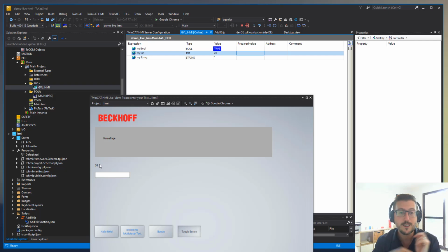So there we go. Where that was starting to go a little bit haywire then, that's a good example of if you are developing on a live machine, this is how you do it. This is how you remain in your development environment and just keep developing and get live values back. And the minute you want to swap back to local, just go back into those ADS settings and swap back to local, or use the profiles. Just swap the profile and it will automatically change it.